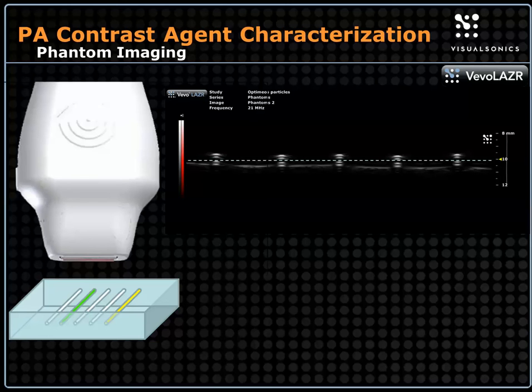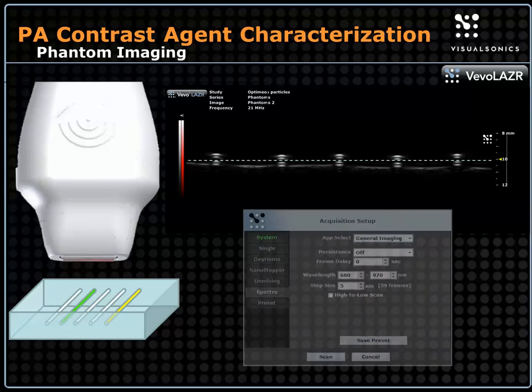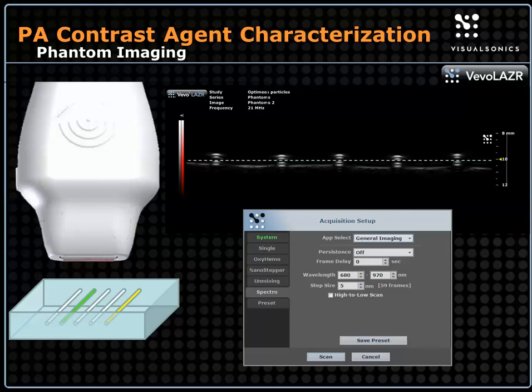There's also a guide we've applied to the software where you can properly line up. The depth of imaging is quite important, so you can properly line up your phantom so that you can do this reproducibly.